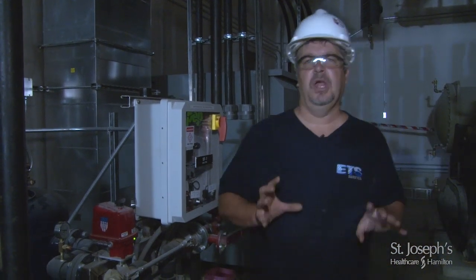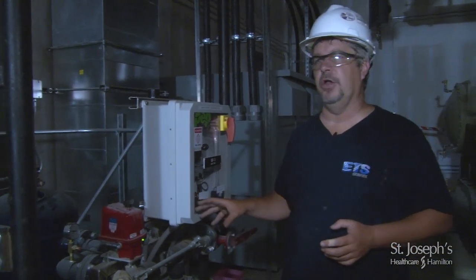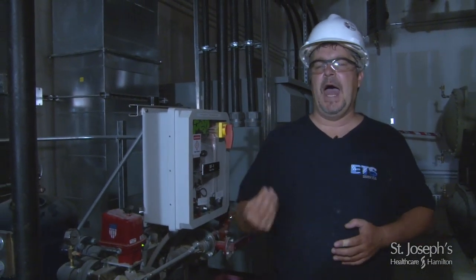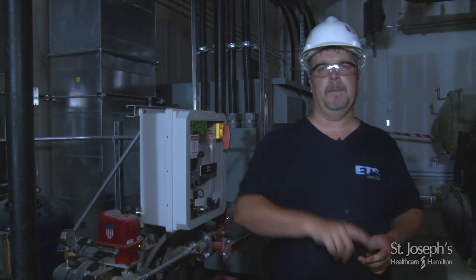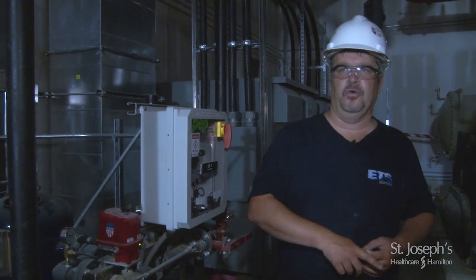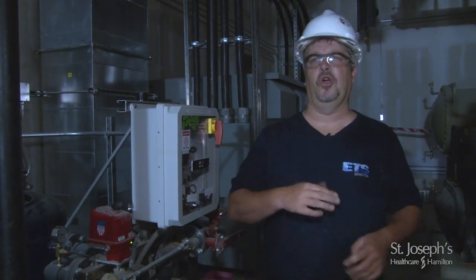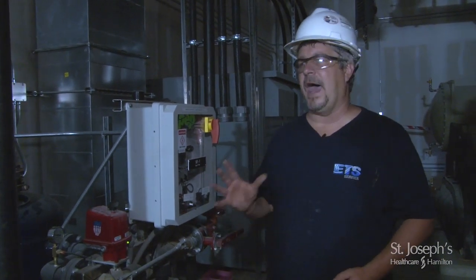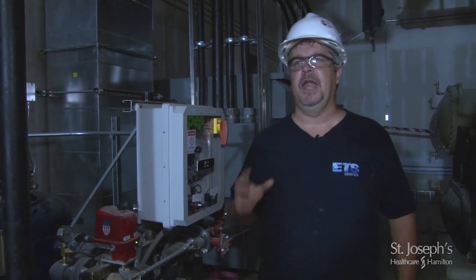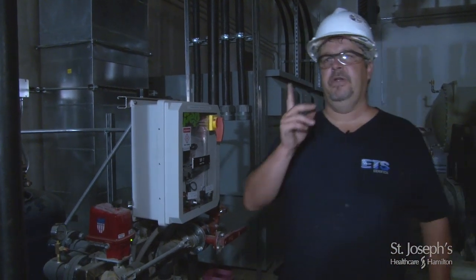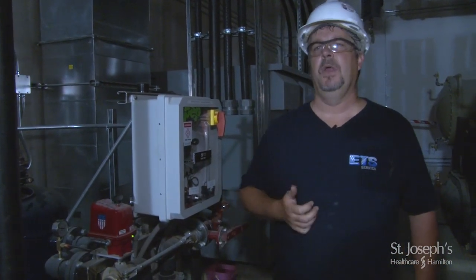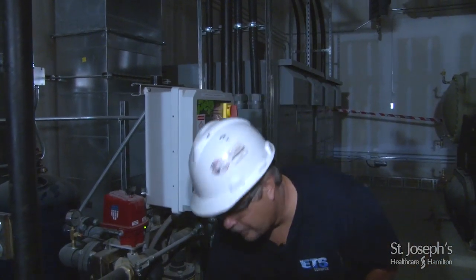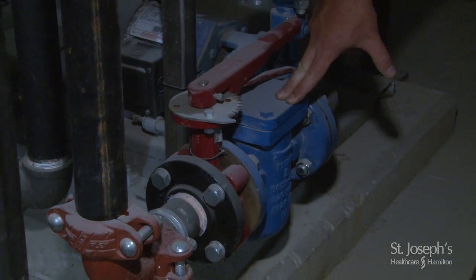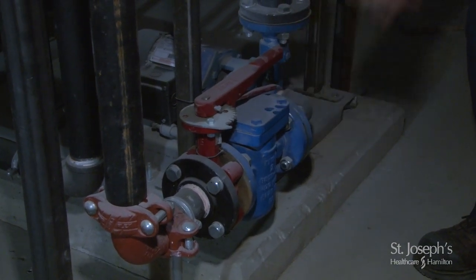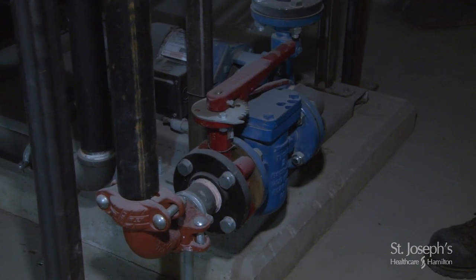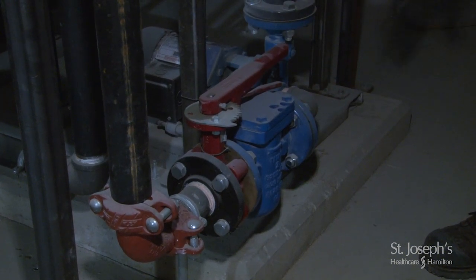Your only indication that something has gone completely wrong with the unit is if you come and the unit is constantly cycling back and forth from backwash to filter, backwash to filter, and never stops that cycle. At that point, you need to turn the unit off and determine what's wrong. The first and 90% of the time, the problem will be right in here. Right inside this cap, like a swimming pool, you have a little skimmer, or filter basket. It's collecting or catching any large particles before they make it into the filter.